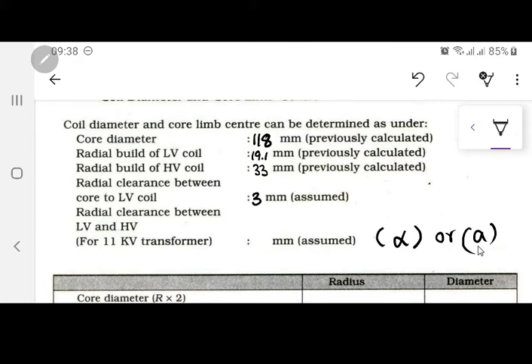But if you keep it far, you are allowing more oil to flow there, and more oil flowing means you are cooling it down. So practically the thermal condition of your transformer is going to be much better. But the leakage flux, or actually the leakage reactance of your transformer, that is percentage X, depends upon this parameter. And in the other book they have written that this parameter can go from approximately 15 mm to 25 mm, for transformers in the range of 200 kVA to 1000 kVA. Since I am designing a very small transformer, a 100 kVA transformer, this book has taken a distance of 10 mm, so I will go with just that.